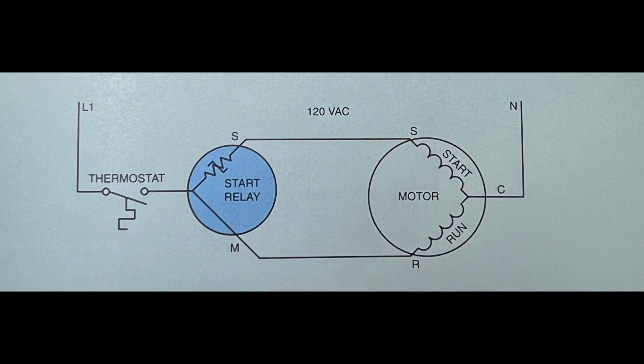When power is first applied to the circuit, the resistance of the thermistor is relatively low, 3 or maybe 4 ohms, and current flows to both the run and start windings. As current flows through the thermistor, its temperature increases. When the temperature becomes high enough, the thermistor suddenly changes from a low resistance to a high resistance, reducing the start winding current to approximately 30 to 50 milliamps. This has the effect of disconnecting the start winding from the circuit. Although a small amount of leakage current continues to flow, it has no effect on the operation of the motor.